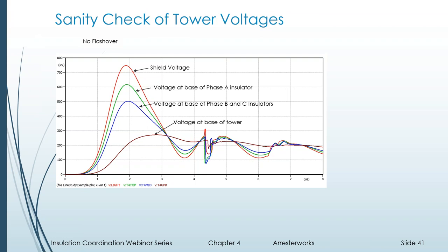In a tower study here, we care about the voltages, but the driving force is the stroke current. So we have to use stroke current as our activator of the whole thing. And then we measure the voltages on the shield, and the voltage at the base of each insulator.